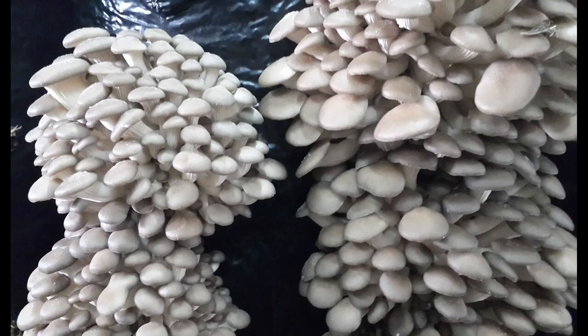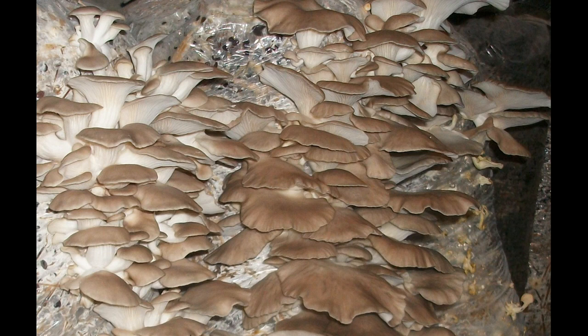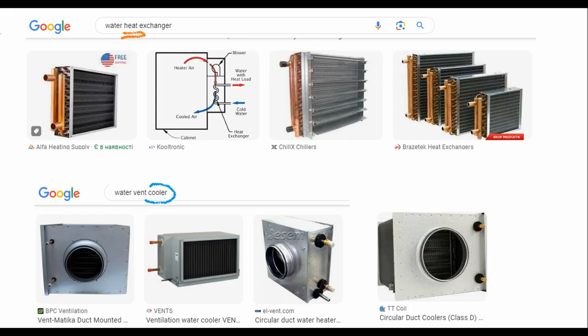There are strains that grow at temperatures from plus 8 to plus 10 degrees Celsius — they are called winter strains. And there is oyster mushroom which grows well at a temperature of plus 26 degrees; in our country such strains are called summer strains. In any case, we need to prepare the air before it enters the chamber — it must have a certain temperature and a certain humidity, and we understand that outdoor air does not have these conditions.